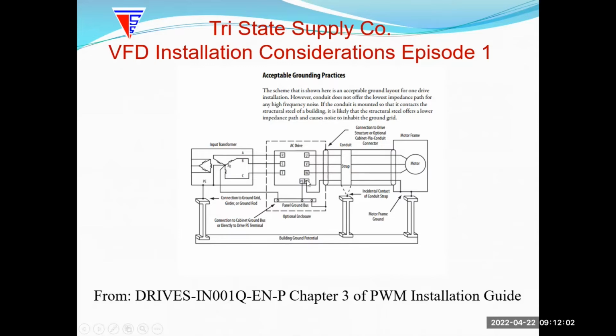This ground, which is recommended to be brought back straight to the drive, to the PE power section of the incoming side or output side of the drive, will help eliminate some of this. But again, because of the high frequency switching noise, you want to consider a shielded cable, which we'll talk about in episode 3.